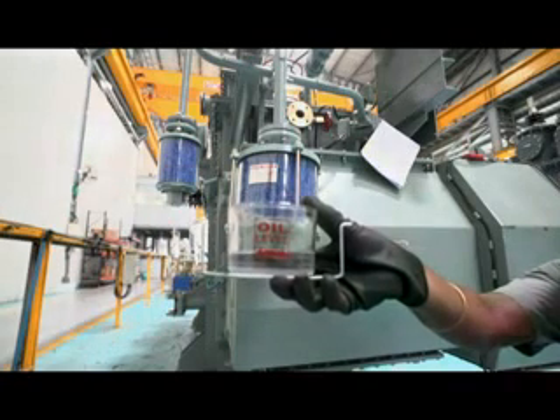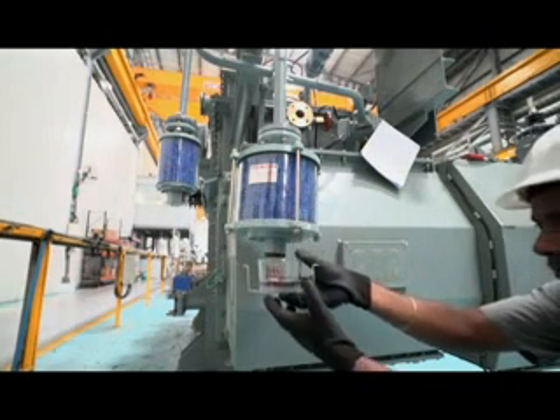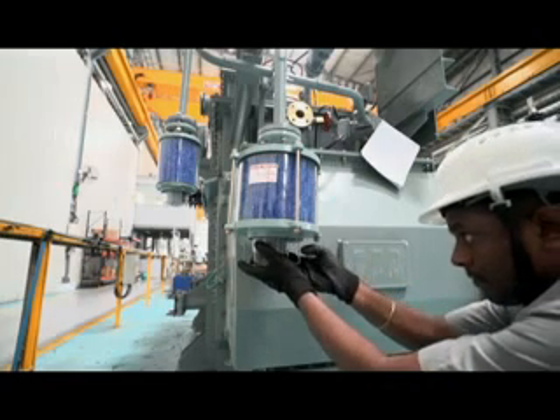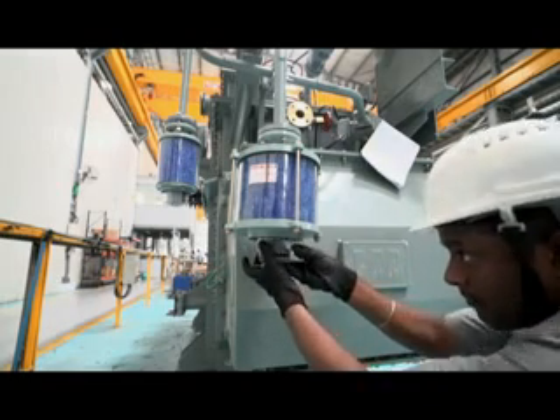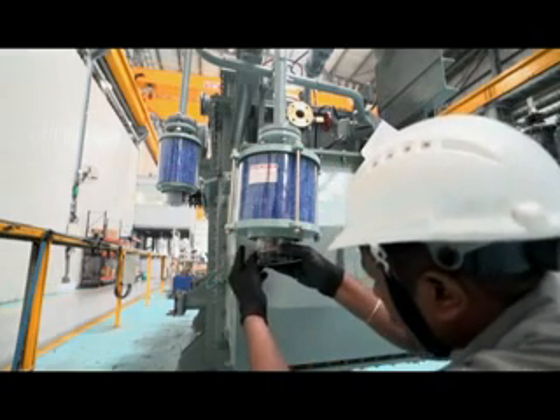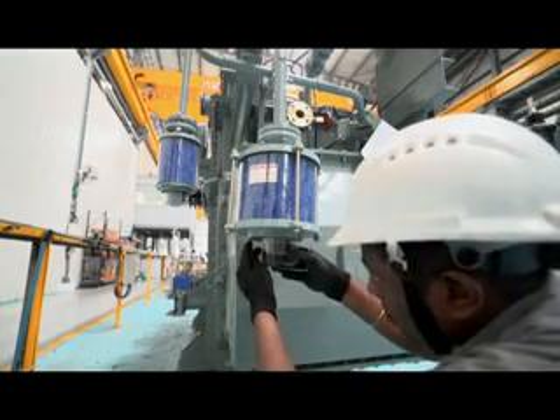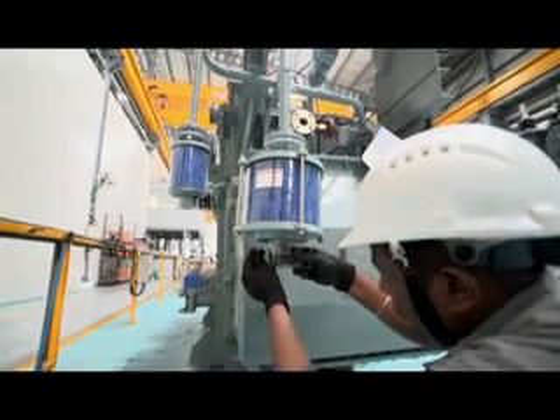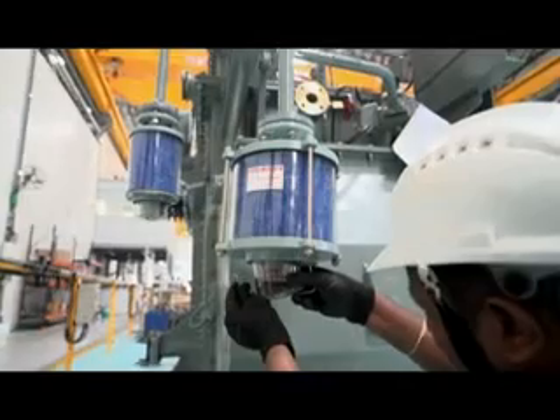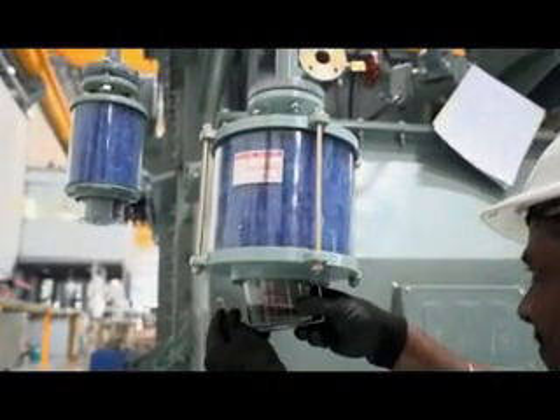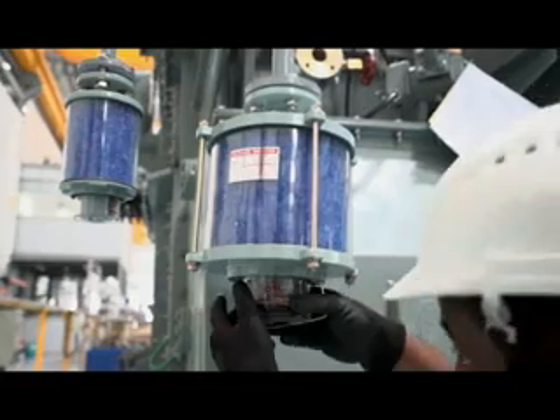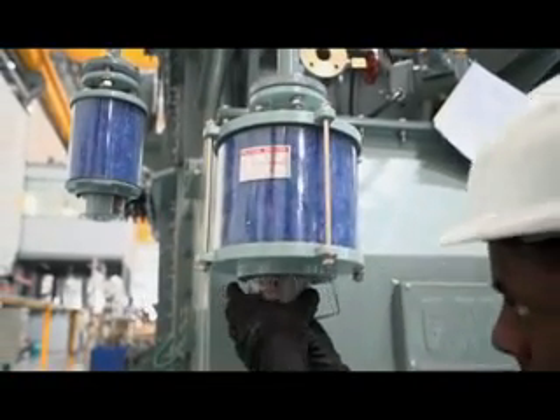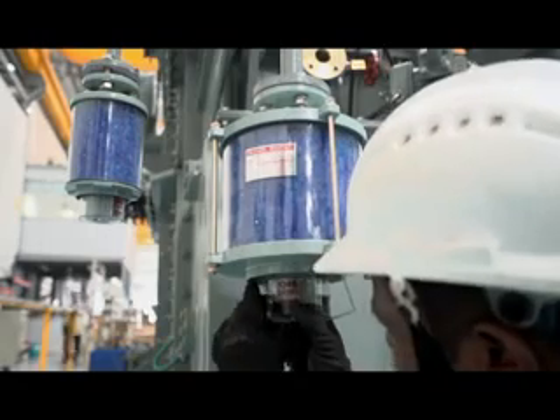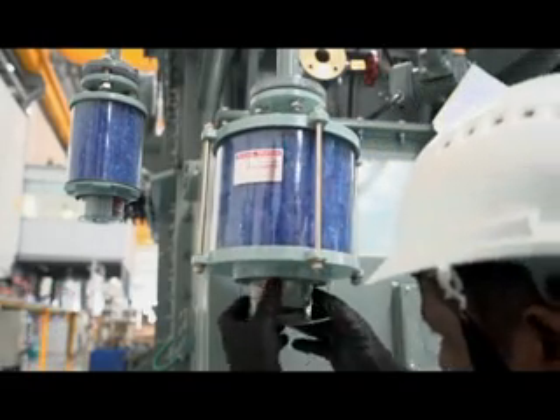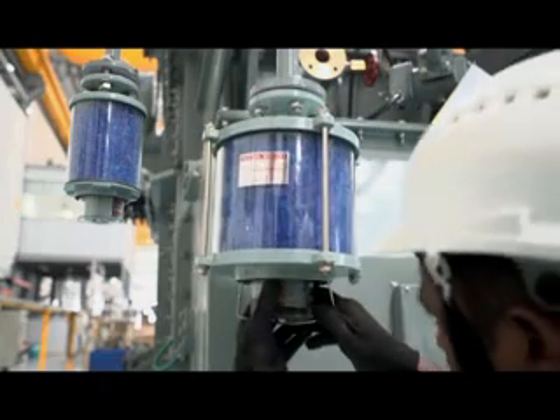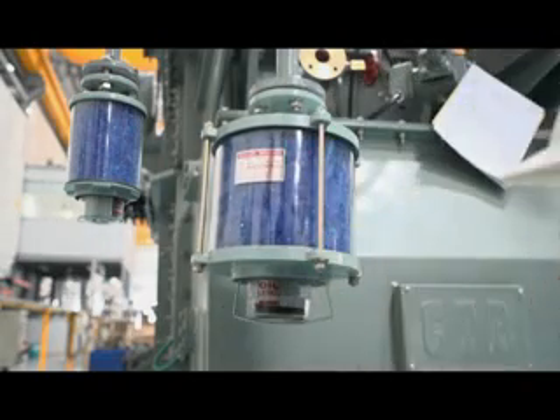The natural air always contains more or less moisture. This moisture can be mixed up with oil if it is allowed to enter the transformer. The air moisture should be resisted during entering of the air into the transformer because moisture is very harmful for transformer insulation. A silica gel breather is the most commonly used way of filtering air from moisture. The silica gel breather for a transformer is connected with the conservator tank by means of a breathing pipe. It is very simple in design. It is nothing but a pot of silica gel through which air passes during breathing of the transformer.